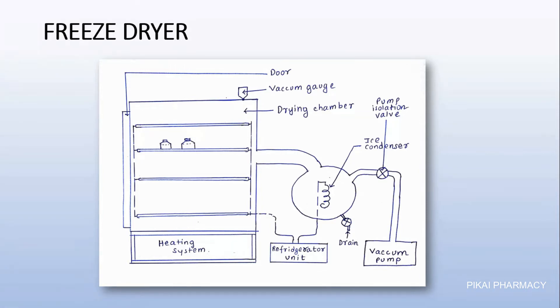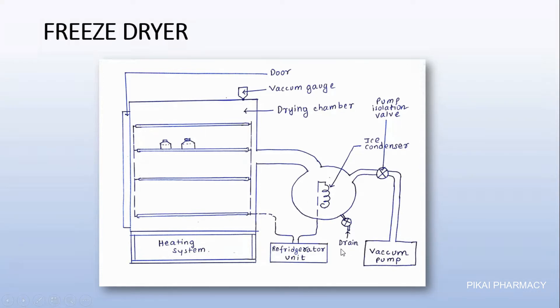At the beginning, there is a refrigerator unit which works first. The sample is placed above the plate and the refrigerator unit decreases the temperature to about minus 20 degrees centigrade, which is very low. At this temperature the moisture content present in our sample becomes ice — it freezes and converts into ice. Then there is a vacuum pump which decreases the pressure, and then the heating system is turned on.